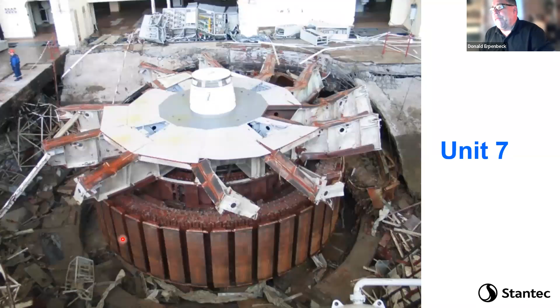Unit 7. Now this is a part of the interesting story besides unit 2. Remember we talked about the bearings in that upper bracket? Well, here the stator is completely gone on the generator. And this bracket was sitting on top of the stator, right? I said that upper guide bearing bracket is sitting on the stationary part. Here's some of the remnants of the stator here, ripped off, and you see the arms, and you also see the torsional pattern that it came off in. The other interesting thing is that all the copper is gone off the rotor poles. There is no copper left on these sitting here.